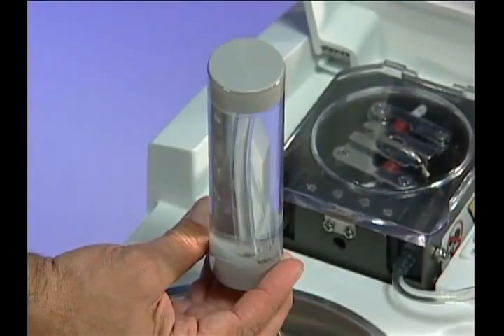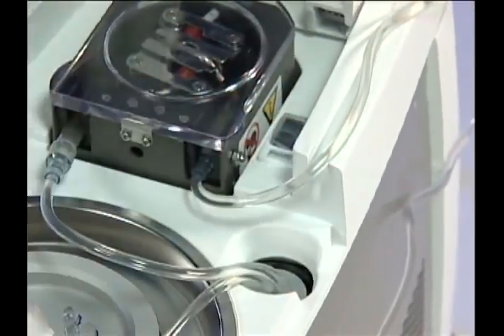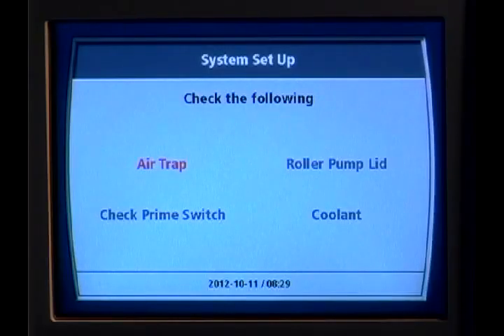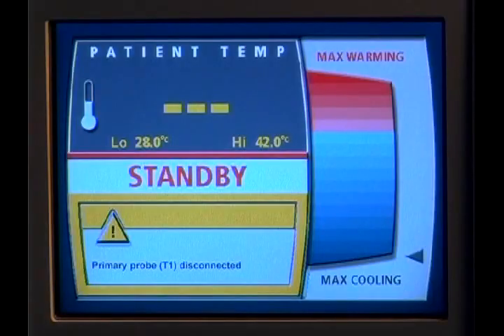Turn the air trap right side up again and place it back in its holder. The system will automatically change from the Check the Following screen to the Standby Operating screen. You will see a yellow system alert message stating that the primary probe, T1, is disconnected. This message will automatically disappear later during the setup procedure while the patient temperature probe is connected to T1.